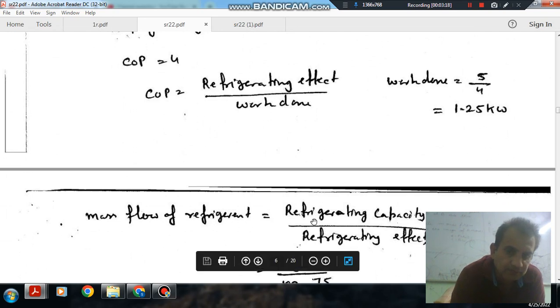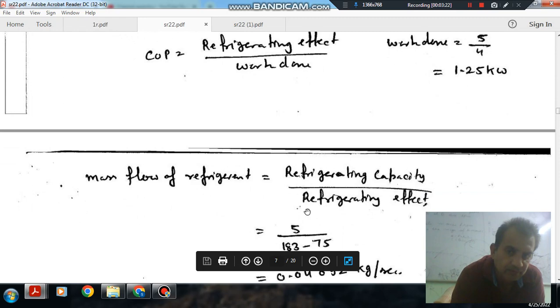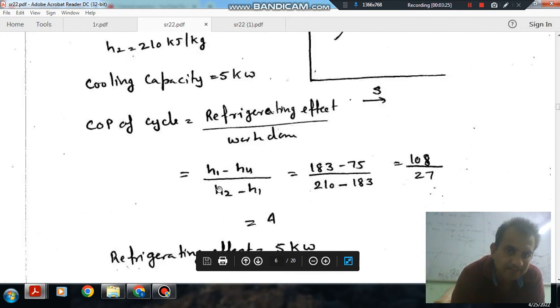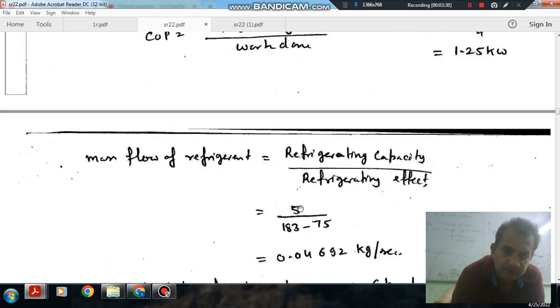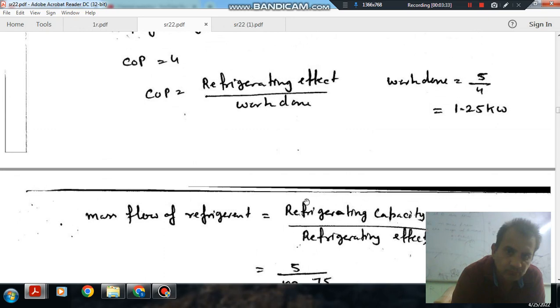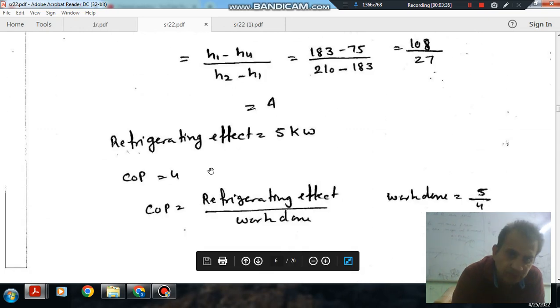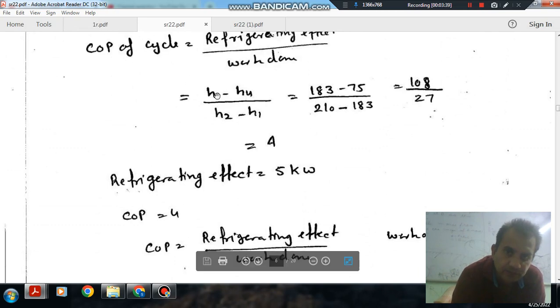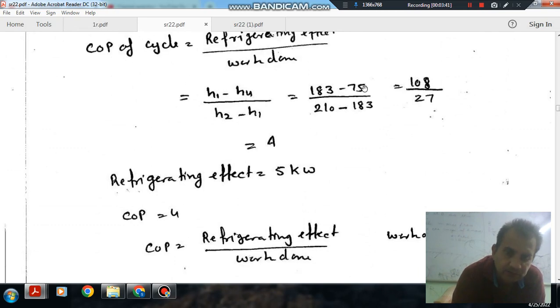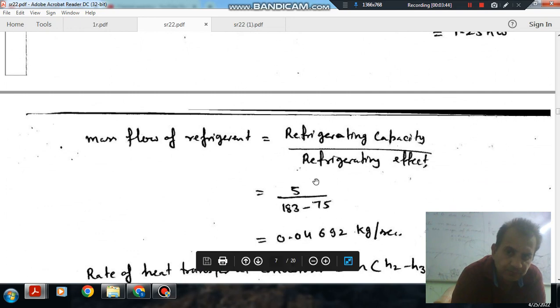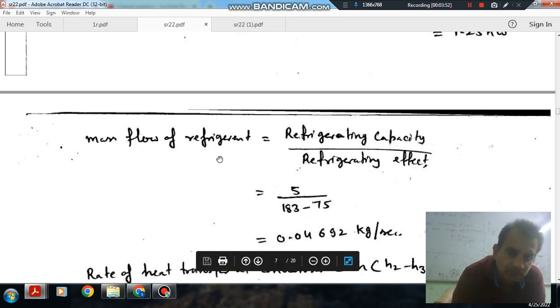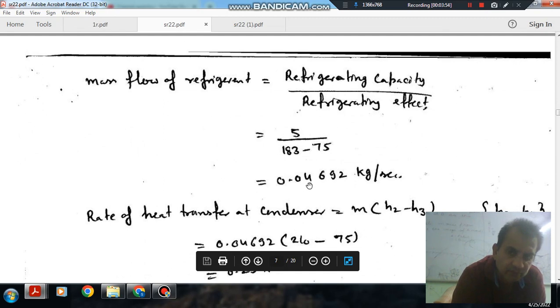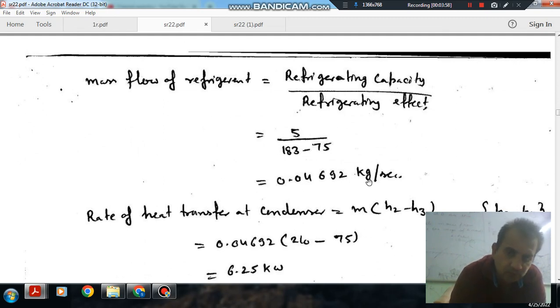The mass flow rate of refrigerant is refrigerating capacity divided by refrigerating effect per kg. Refrigerating capacity is 5 kW, and refrigerating effect per kg is H1 minus H4. From this we can calculate the mass flow rate of refrigerant, which comes out to 0.04629 kg/s.